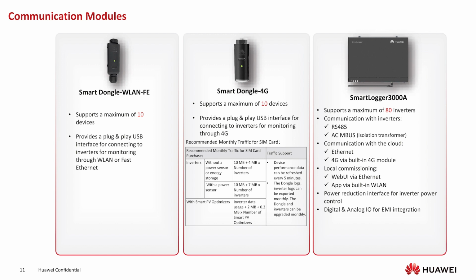Communication modules: we've got the Smart Dongle WLAN. This supports up to 10 devices. So if you are using anything from 1 to 9 inverters or 10 inverters, then you could use the Smart Dongle. It's much cheaper than the Smart Logger, okay?